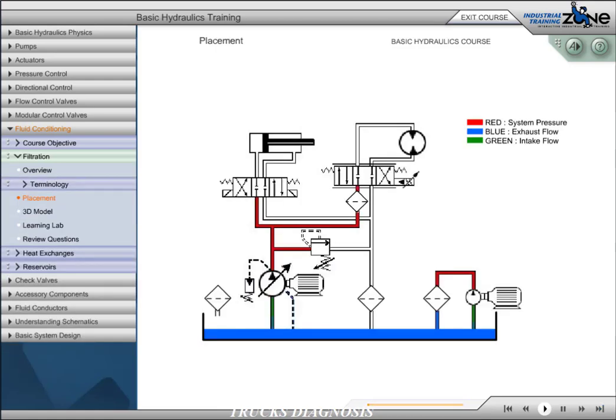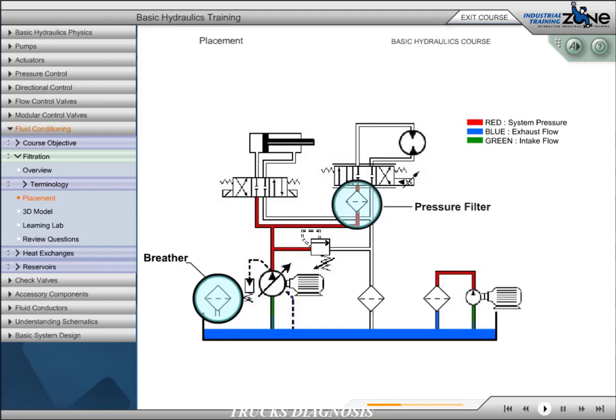Filter placement is critical for maintaining acceptable fluid cleanliness levels, adequate component protection, and reducing machine downtime. Filter breathers are critical in prevention of airborne particulate ingression. As the system operates, the fluid level in the reservoir changes, drawing in outside air and with it airborne particulates. The breather filters the air entering the reservoir. Pressure filters are often required to protect the component immediately downstream, such as a sensitive servo valve, from accelerated wear, silting, or sticking. Pressure filters must be able to withstand the operating pressure of the system, as well as any pump pulsations.